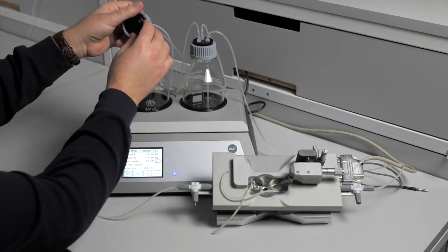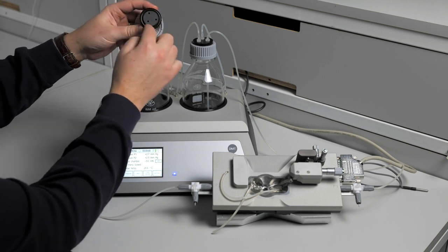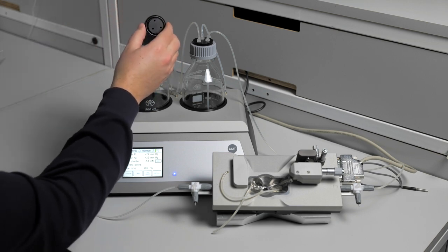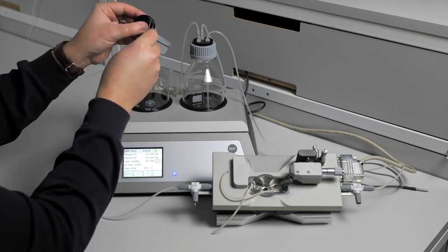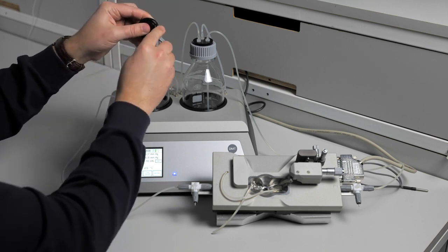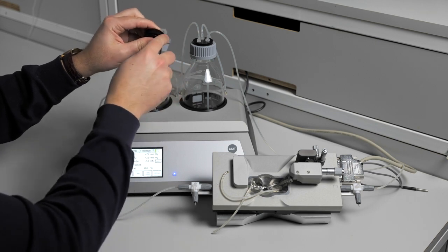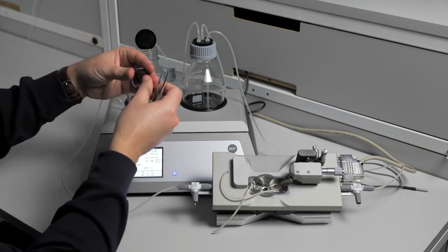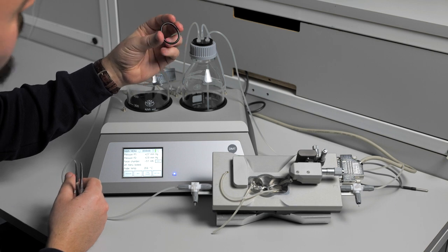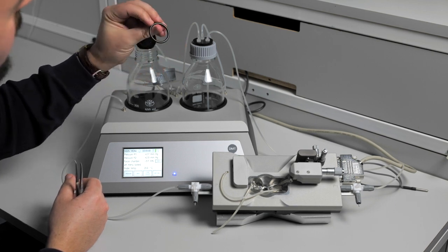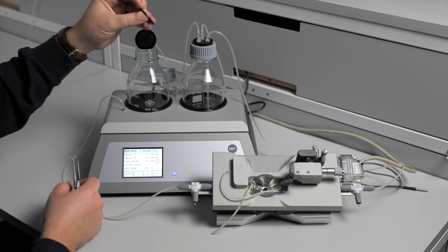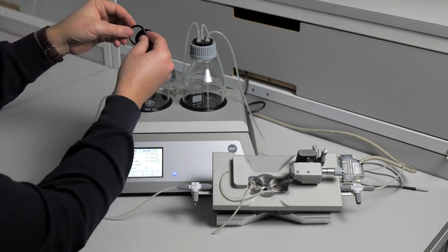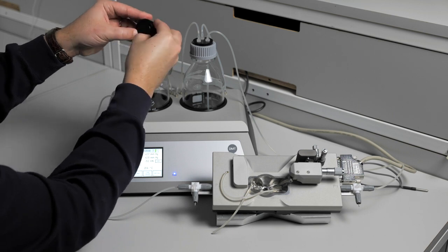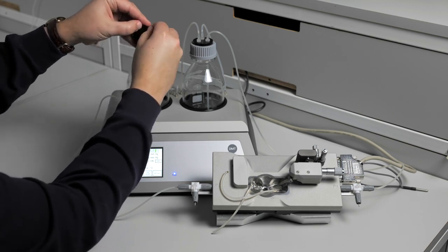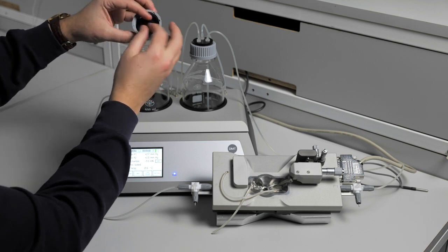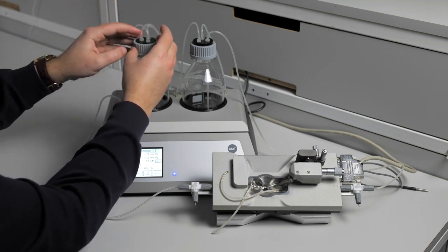Loosen the cap, and we're going to look at the O-ring that's in this cap. Take your forceps and pull this O-ring out of the cap. You want to look and make sure that there are no cracks in the O-ring. If there is a crack, that means that pressure is escaping and will be the cause of your pressure leak. If the O-ring looks good, put it back in the cap and tighten the cap securely on top of the bottle.